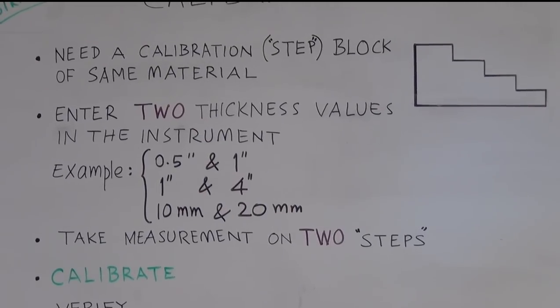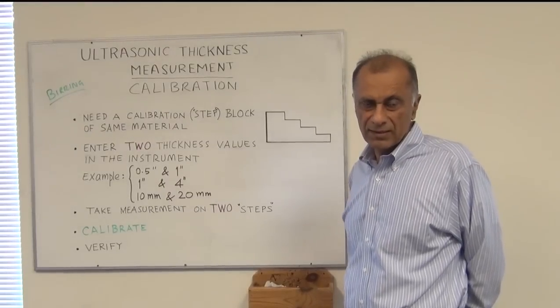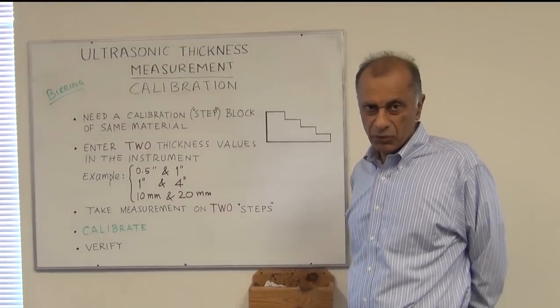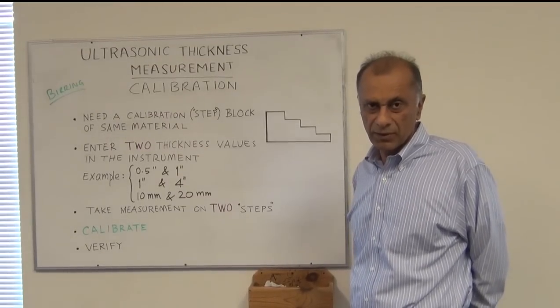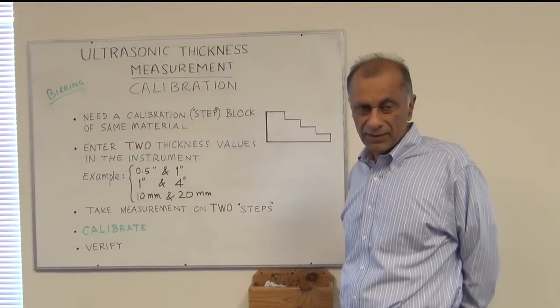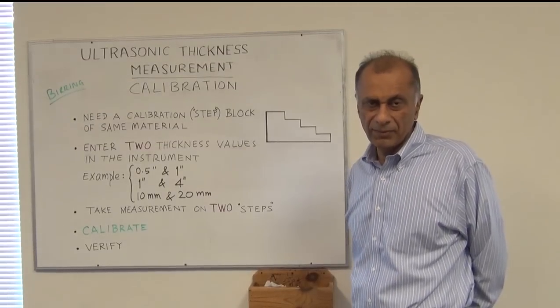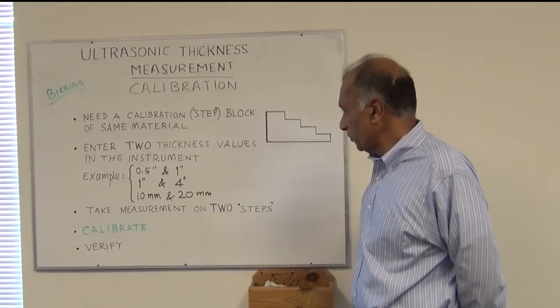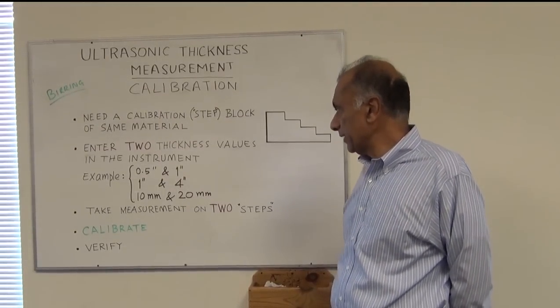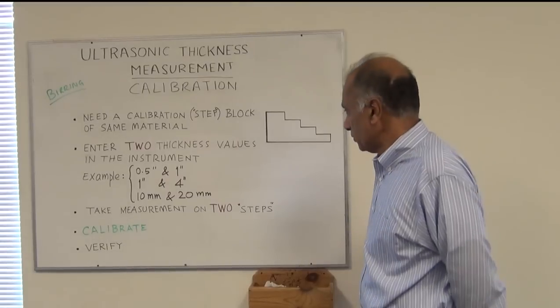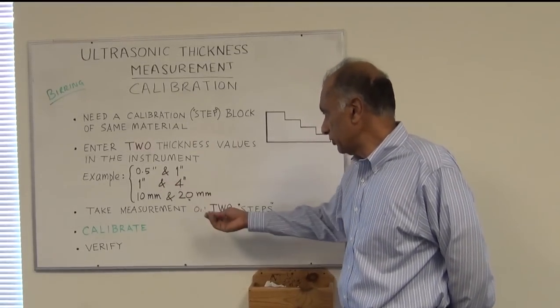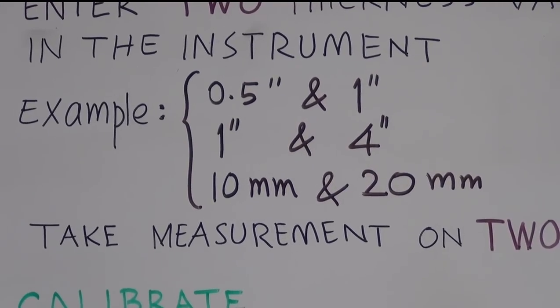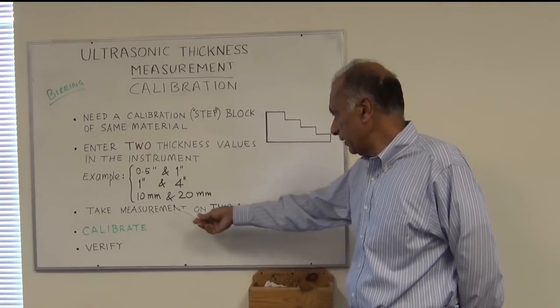First of all you need a step block with known thicknesses, normally a four step block or five step block. The four steps could be quarter inch, half inch, three quarter inch and one inch, or if it's in metric it would be 5mm, 10mm, 15mm, 20mm and 25mm. After that we select two thicknesses from the step block which could be for example half inch and one inch, or if you are using an IIW block then it would be one inch and four inch, or if you are using metric it could be 10 and 20mm.